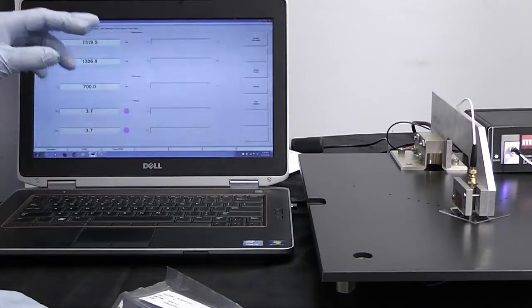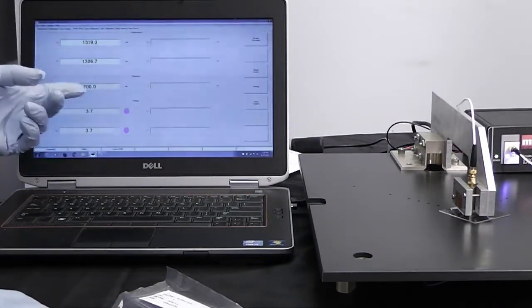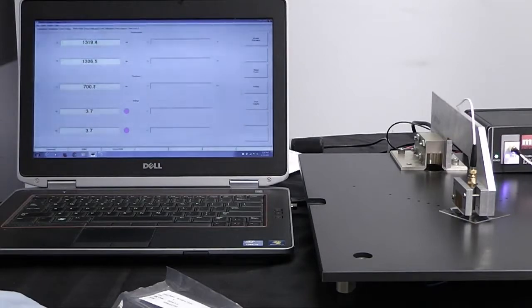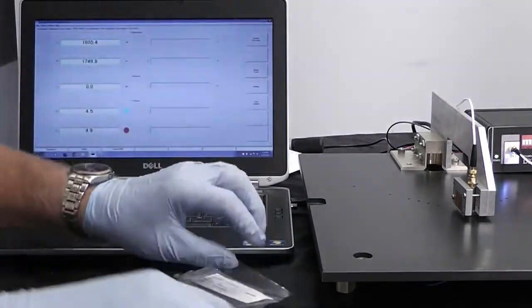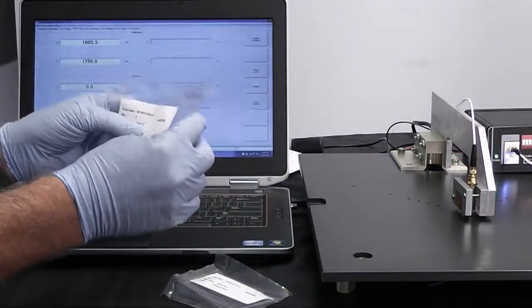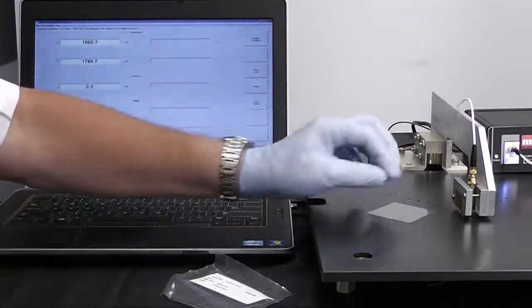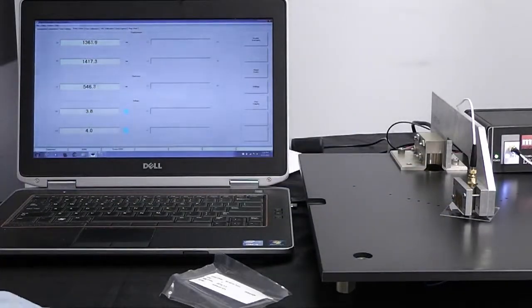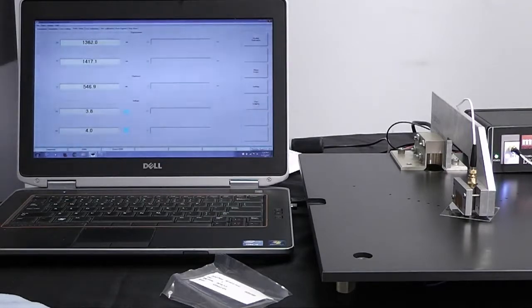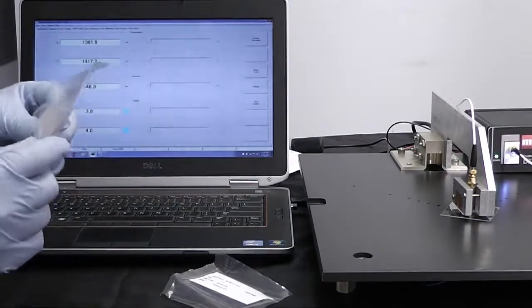Enter that. So I'm reading 700 microns for this sample. The manufacturer says it's 700 microns. We're going to look at next a 550 micron sample. And we're reading within 3 microns of that sample, which is well within the accuracy of what they were stating on their envelope here.